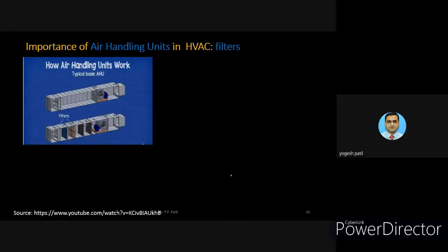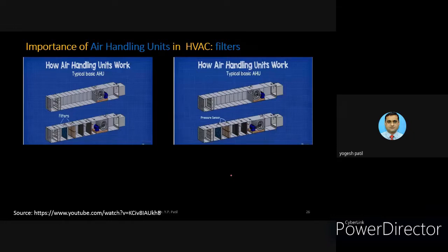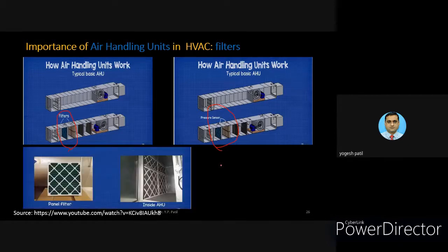Then there are filters, the third part. On filters there is also the instrumentation part. You can see over here the filters, and the pressure is required to be measured to maintain the life of the filters. How much pressure difference is created over there can be measured with the help of different types of pressure sensors.